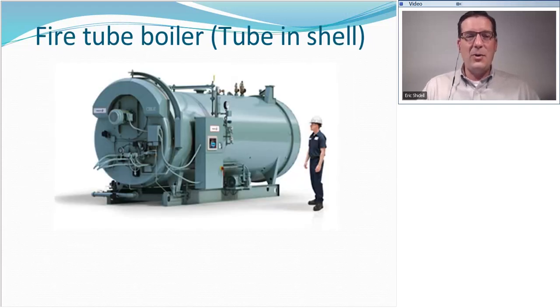The next boiler we're going to talk about is called the fire tube boiler. Now, the other one was a water tube boiler because it had water running through tubes. Guess what this one has? Fire running through tubes, also known as tube in shell. They look like a giant coffee can tipped over on its side, and they are giant. This gentleman here is standing next to, I would say, a medium-sized fire tube boiler. And yes, they are big. You're going to need a ladder if you want to reach up to the top of one.